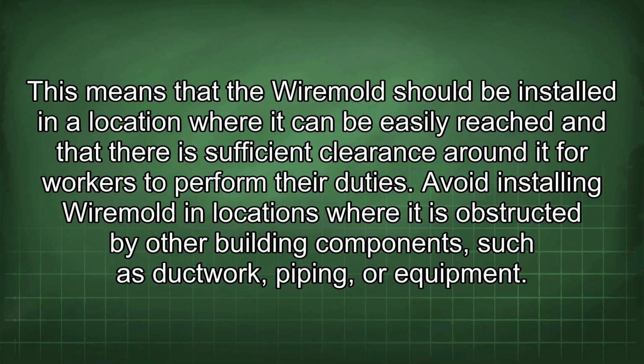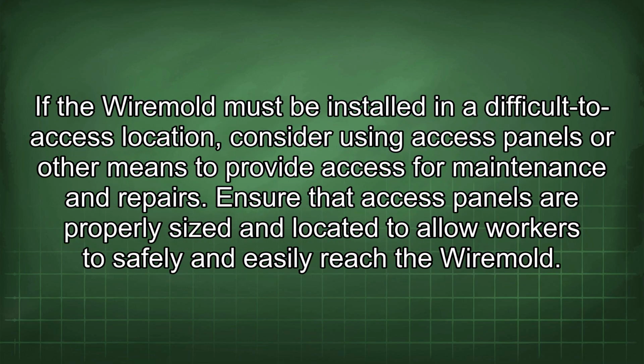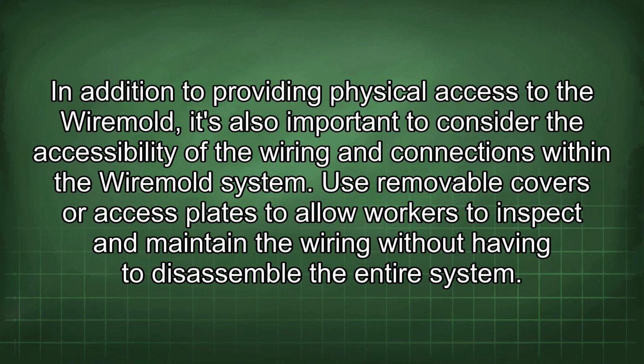Avoid installing Wiremold in locations where it is obstructed by other building components such as ductwork, piping, or equipment. If the Wiremold must be installed in a difficult-to-access location, consider using access panels or other means to provide access for maintenance and repairs. Ensure that access panels are properly sized and located to allow workers to safely and easily reach the Wiremold. In addition to providing physical access to the Wiremold, it's also important to consider the accessibility of the wiring and connections within the Wiremold system.